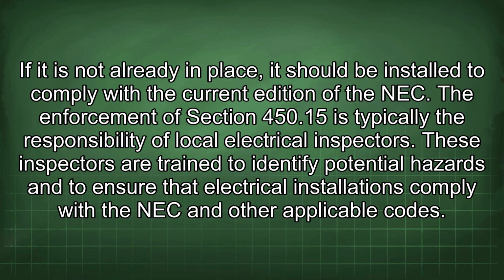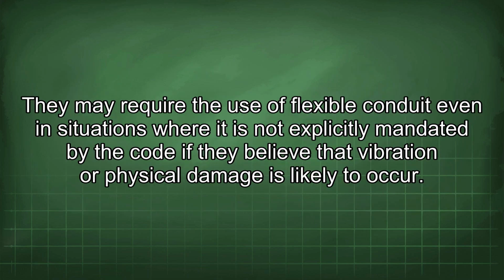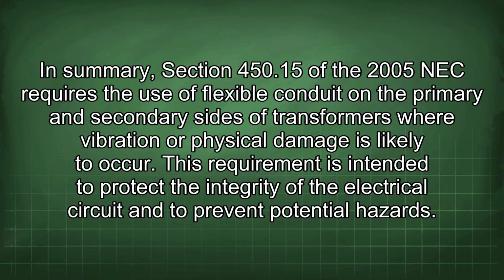These inspectors are trained to identify potential hazards and to ensure that electrical installations comply with the NEC and other applicable codes. They may require the use of flexible conduit even in situations where it is not explicitly mandated by the code if they believe that vibration or physical damage is likely to occur.